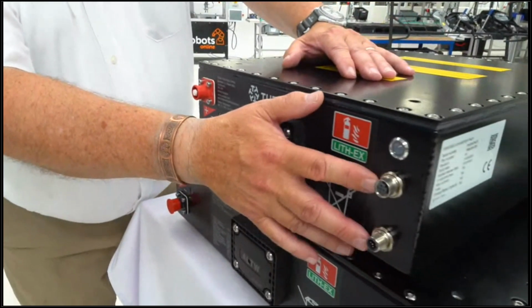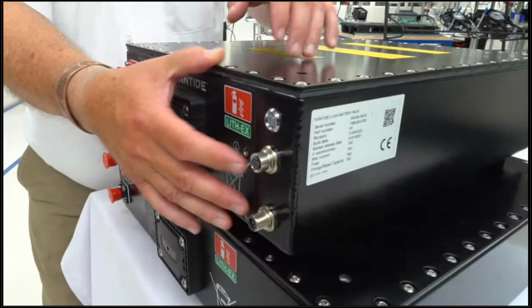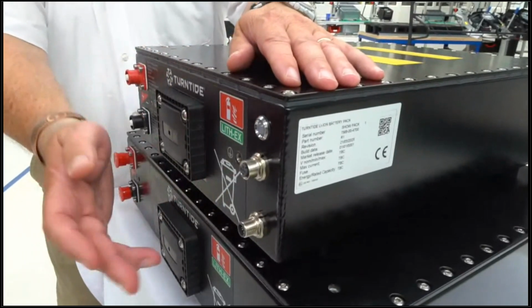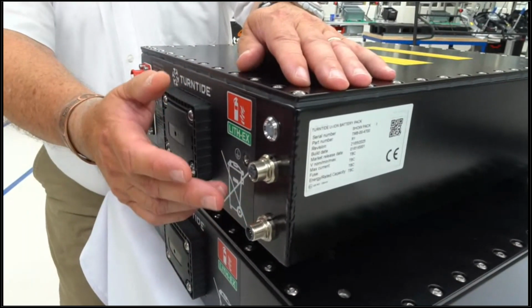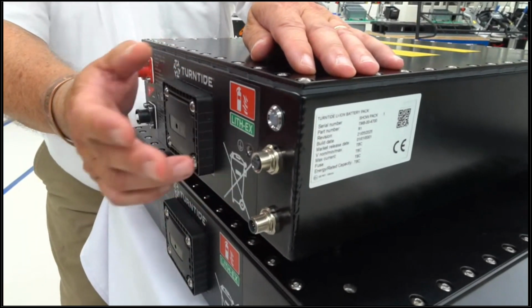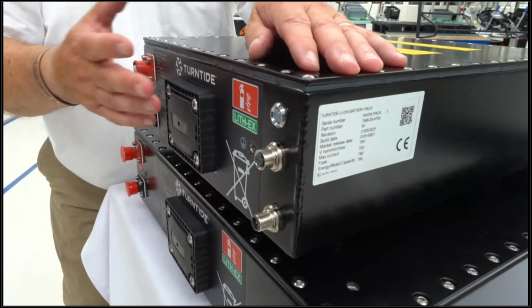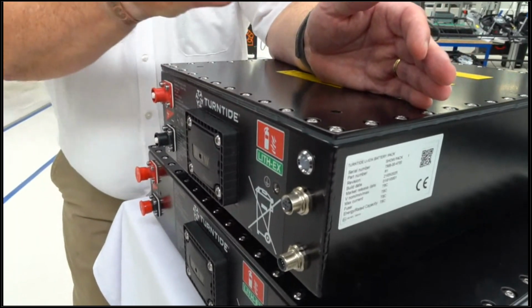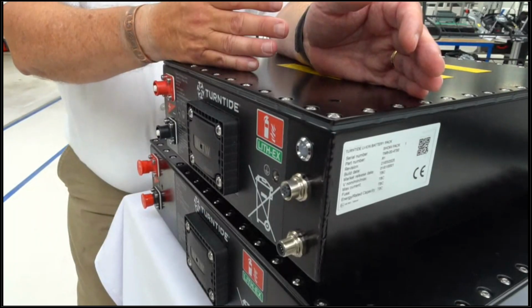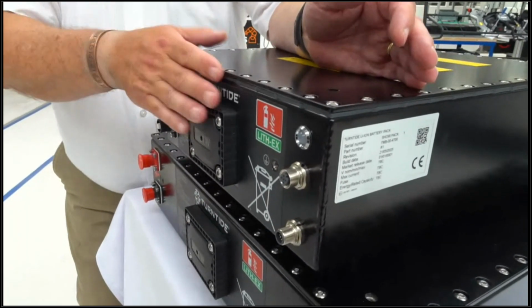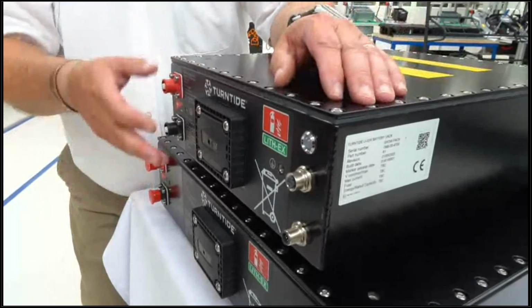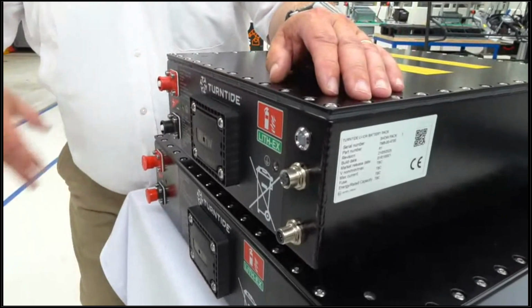On this side, again, it's a daisy chain concept - all of the modules can be daisy chained together with an input and an output on these M12 connectors. They feed all the information from inside the pack on temperature, voltage, and current. So the status within the module all goes back to the BCU, the battery control unit, where all of the state of charge and state of health calculations are made.